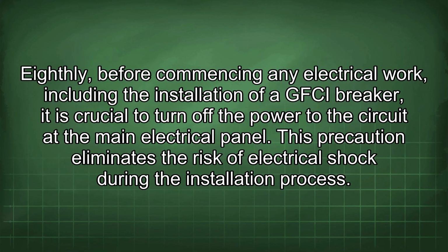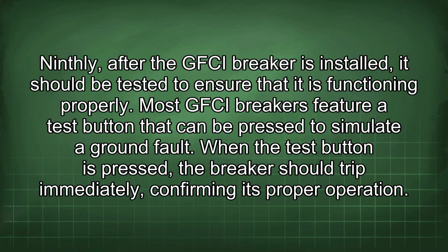Eighthly, before commencing any electrical work, including the installation of a GFCI breaker, it is crucial to turn off the power to the circuit at the main electrical panel. This precaution eliminates the risk of electrical shock during the installation process. Ninthly, after the GFCI breaker is installed, it should be tested to ensure that it is functioning properly. Most GFCI breakers feature a test button that can be pressed to simulate a ground fault. When the test button is pressed, the breaker should trip immediately, confirming its proper operation.